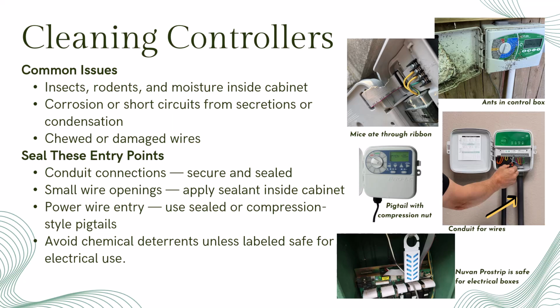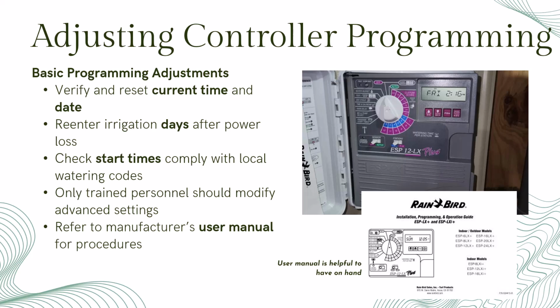moisture and insects out. A quick technician's note: never throw ant bait or chlorine tablets inside the cabinet. The fumes are caustic and can damage the electrical components. Only use deterrents specifically labeled as safe for electrical equipment. Adjustments to a controller are usually simple. They're often done as part of a maintenance visit.